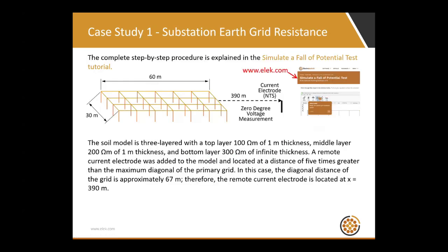Let's look at one case study, and we'll look at two. It's a simple but not uniform, not symmetrical grid, a medium size earthing system. It's 60 meters by 30 meters. We've got lots of rods. We are assuming a sort of random 3-layer soil: 100 ohm meters in the first layer of 1 meter thickness, then a middle layer of 1 meter thickness of 200 ohm meters, and a bottom layer of infinite thickness. So we've got increasing soil electrical resistivity, a 3-layer soil model, and we've simulated this grid in the model, and we've simulated a current injection point, or we've added an electrode, and we have injected current in that point.